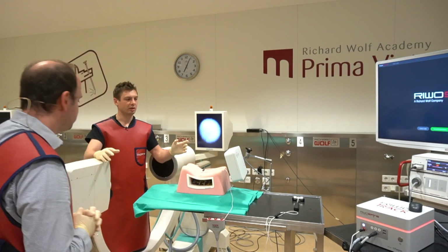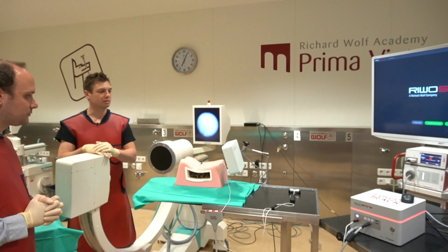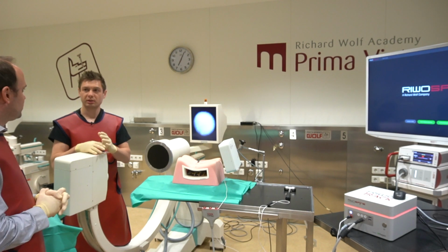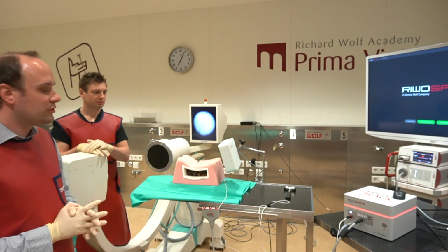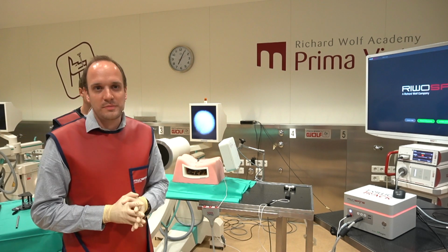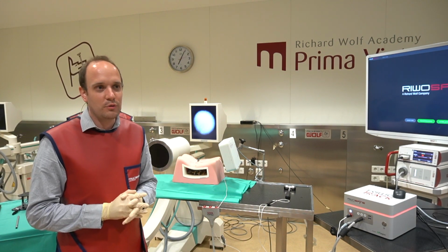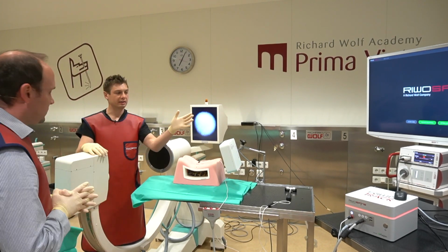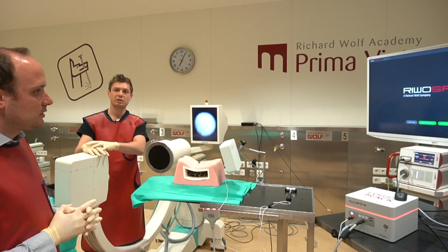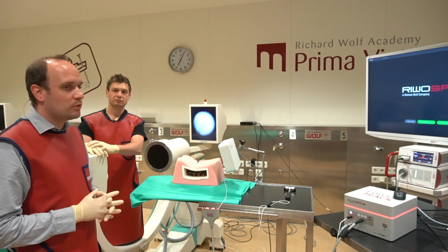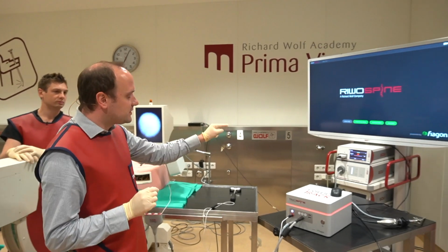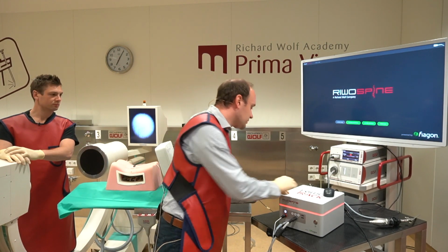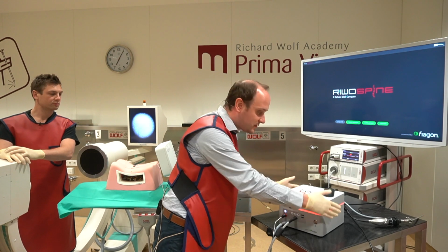A question, Frederick. We see this standing beside the tower. Do I need a special table for the RIWOtrack, or where do I position that in the OR? You can place it on the tower, or on a special table, depending a little on the setup of your tower. But usually there will be space on the tower. And how is this connected to my tower? Do I need a Wolf tower, or how does it work? A Wolf tower would be best because the image quality is the best. We get the HDMI signal, the 4K signal from our Logic camera, and we have it plugged in the back end side of this box.